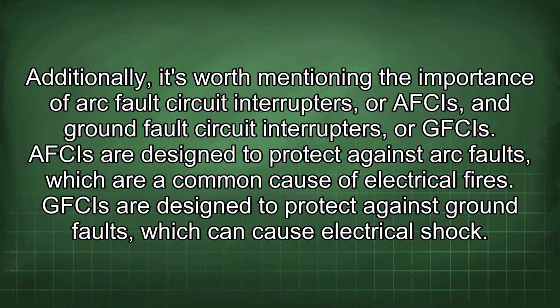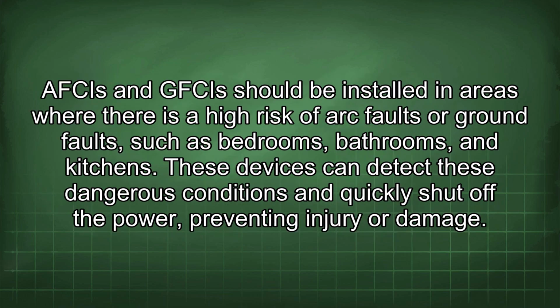Additionally, it's worth mentioning the importance of arc fault circuit interrupters, or AFCIs, and ground fault circuit interrupters, or GFCIs. The AFCIs are designed to protect against arc faults, which are a common cause of electrical fires. GFCIs are designed to protect against ground faults, which can cause electrical shock. AFCIs and GFCIs should be installed in areas where there is a high risk of arc faults or ground faults, such as bedrooms, bathrooms, and kitchens. These devices can detect these dangerous conditions and quickly shut off the power, preventing injury or damage.